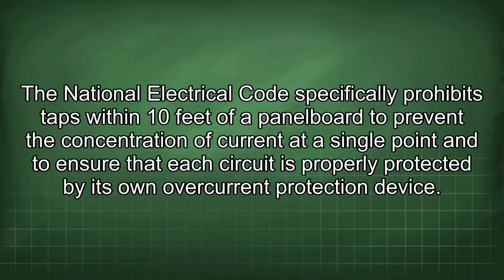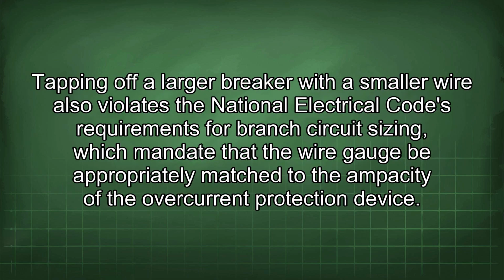The National Electrical Code specifically prohibits taps within 10 feet of a panel board to prevent the concentration of current at a single point and to ensure that each circuit is properly protected by its own overcurrent protection device. Tapping off a larger breaker with a smaller wire also violates the National Electrical Code's requirements for branch circuit sizing, which mandate that the wire gauge be appropriately matched to the ampacity of the overcurrent protection device.